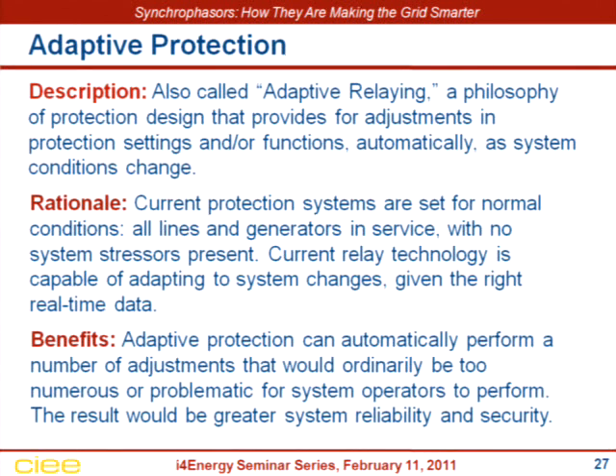However, as we're finding out in a lot of this post-disturbance analysis from blackouts, relays do not operate correctly in all cases, particularly when the system is highly stressed, when there are multiple outages leading to a cascading outage. And it's been documented, not only in this 96 blackout, but also in the 2003, 2004 blackouts of more recent vintage, that relays were tripping out lines, tripping out generators, when analysis showed you'd rather they didn't do that. But they had no way of knowing, they had no way of adapting to the conditions. So what we're doing is demonstrating on a PG&E Southern Cal Edison transmission line how to do adaptive relaying.